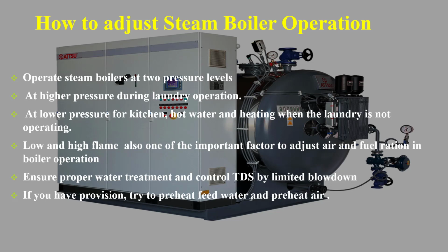Low and high flame is also one of the important factors to adjust the air and fuel ratio in boiler operation. Ensure proper water treatment and control total dissolved solids by limited blowdown. If you have provision, try to preheat feed water and preheat air.